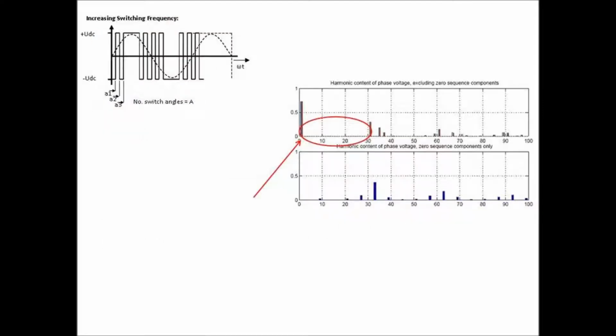So there are lots of different devices in eWIC that make it work. The voltage source converter itself is actually quite good at blocking harmonics. If you set a high enough number of switching angles, and we've got 11 in this case, it's able to eliminate about 10 harmonics. So a lot of the spectrum from 0 all the way up to 30 is eliminated by the converter itself, which meant we didn't need too many filters involved.